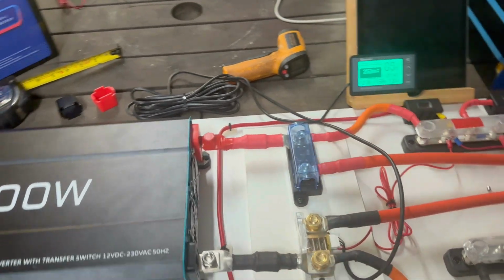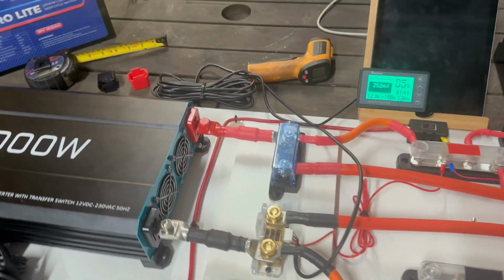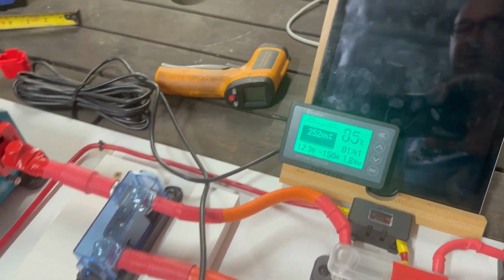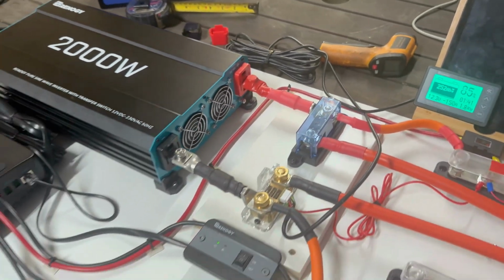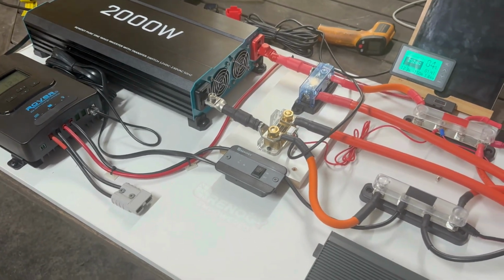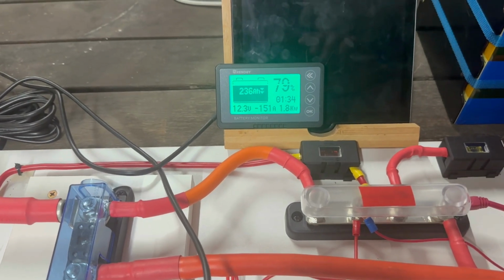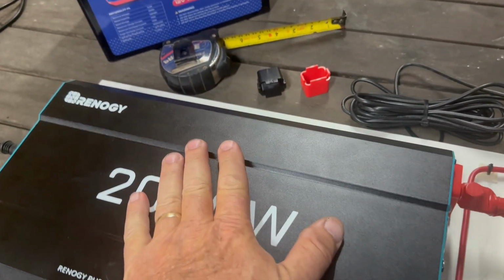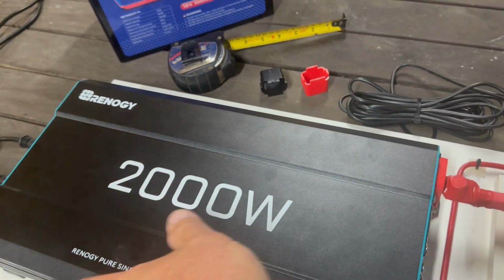I'm going to let that run for a bit longer now. I'll probably pull that battery down to, say, 80% capacity, and we'll see where we're at then. So down to 79% on the battery capacity, still running that 1.8 kilowatt load continuous, and it's doing it fine. Look, it's really not heating up.